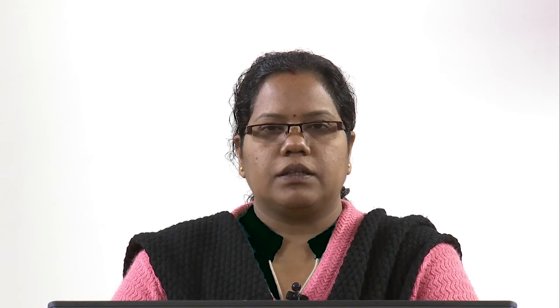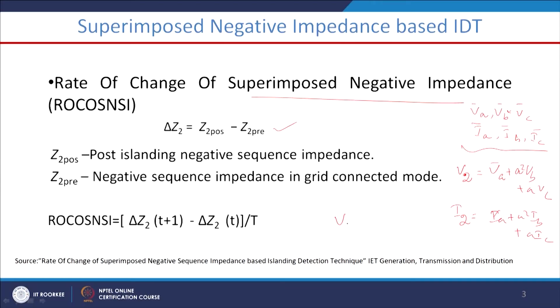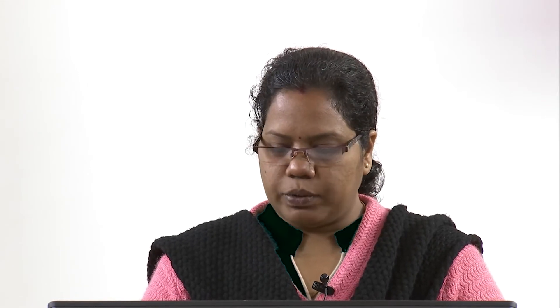One important point: our distribution network is mostly unbalanced in nature. Due to the presence of single-phase loads, unbalancing occurs, so negative sequence voltage and negative sequence current are both present even before any disturbance or before islanding mode of operation. By exploiting this V2_pre and I2_pre information, we calculate Z2_pre — the negative sequence impedance of the microgrid system at the DER terminal when the system is not disconnected — as Z2_pre = V2_pre / I2_pre.